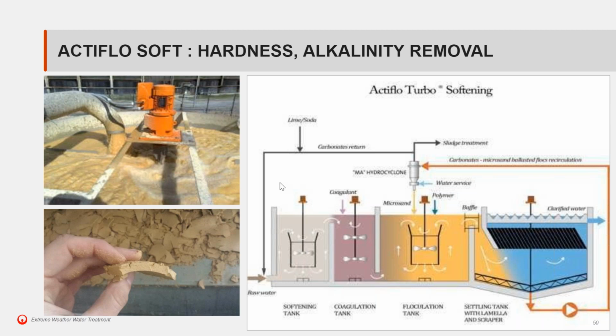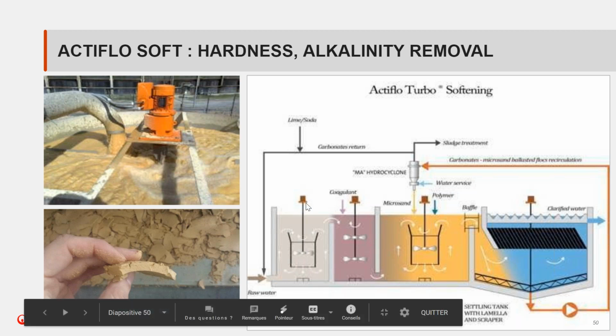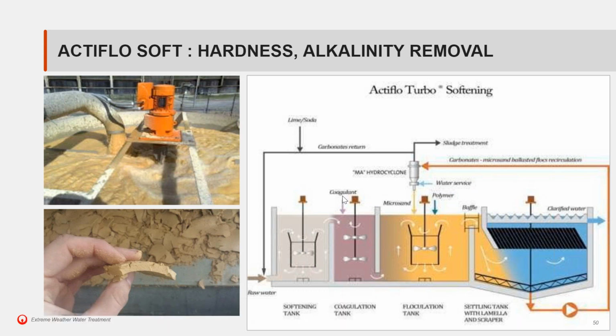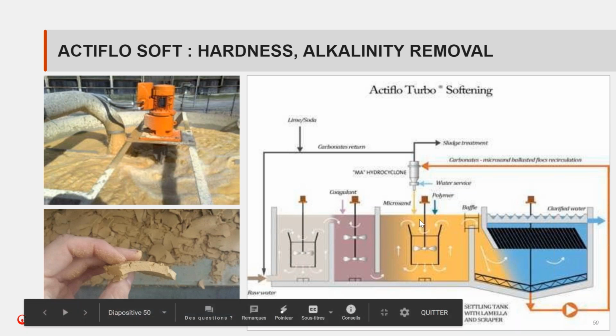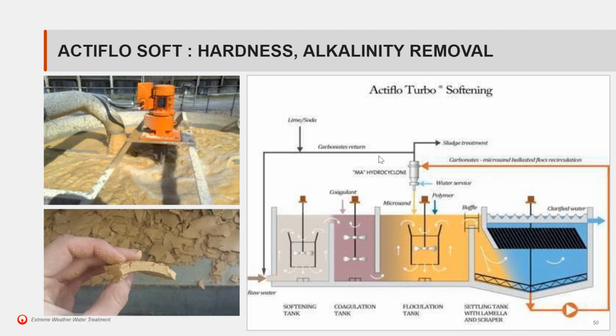It is very similar to Actiflo Carb in the sense that there is a pre-contact tank where we introduce lime slurry or caustic soda, and we mix it with recirculated carbonate sludge. We then introduce coagulant in the coagulation tank and microsand, and polymer to bind all these carbonate to the floc and settle. In order to enhance the performance and, more importantly, to act as a catalyst of the CaCO3 particle formation, we recirculate sludge. This is why the process is so effective. It's based on the cold lime softening process.